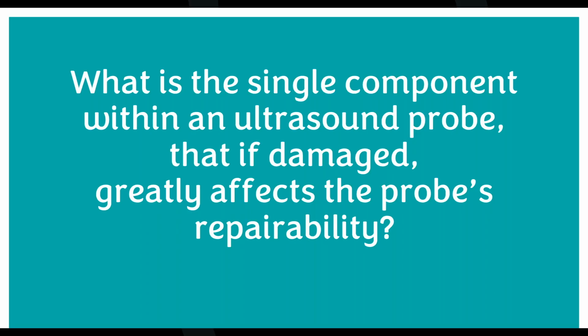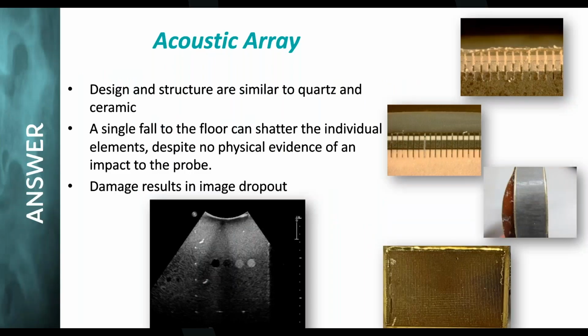What is a single component within an ultrasound probe that, if damaged, greatly affects the probe's repairability? Yep, the acoustic array. There are newer arrays coming out today, these matrix arrays, that are not even a conventional array, they're a chip. So these are conventional arrays.